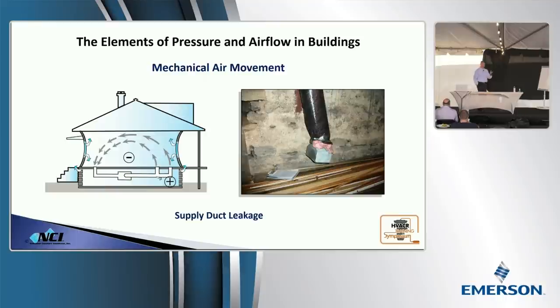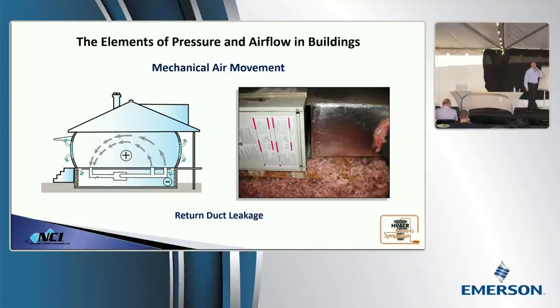Now, on the flip side of supply side leakage, what about return side leakage? With return side leakage, it's the exact opposite. Now you're blowing air into the space, but you may be pulling it from someplace else. So as we look at air, we have to consider how it influences the system, and how it influences any combustion equipment located inside that space. Any questions or comments so far? Appreciate your comments. Now, duct leakage is pretty simple.